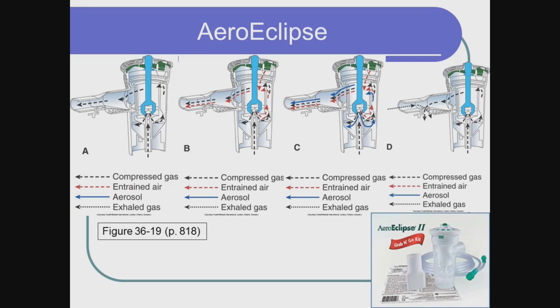Is it the busiest slide you've ever seen? It's like, what the hell is it saying? It's saying that it only delivers medication during the inspiratory phase and shuts itself off during the expiratory phase.